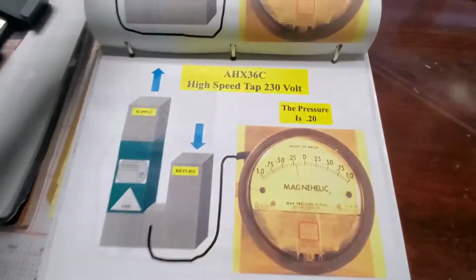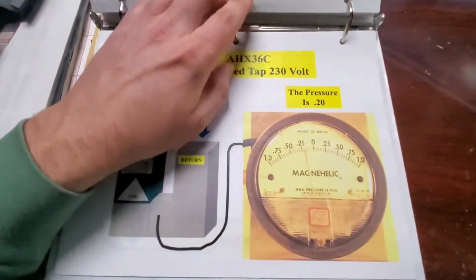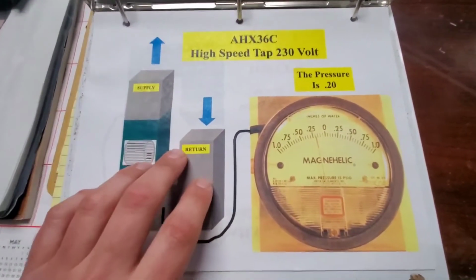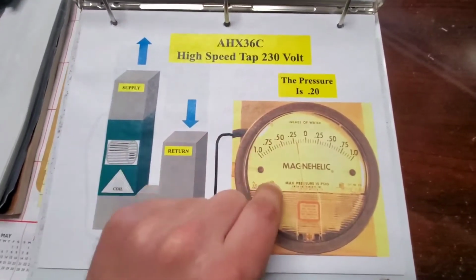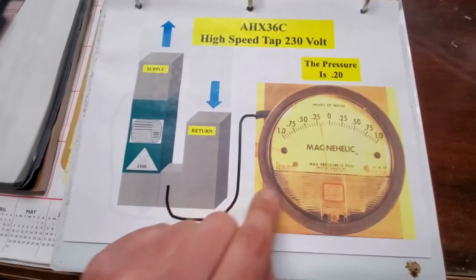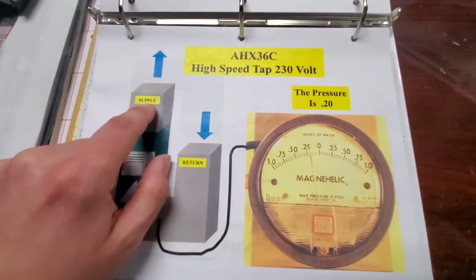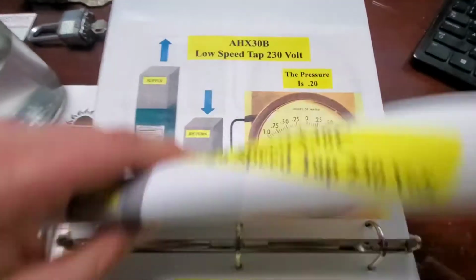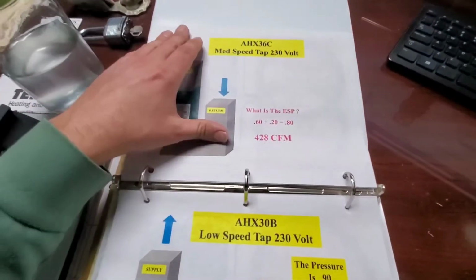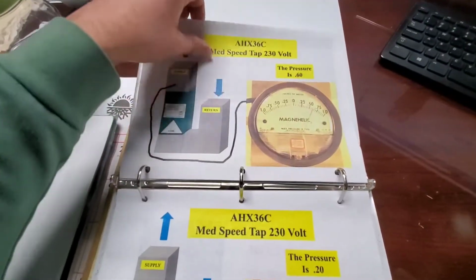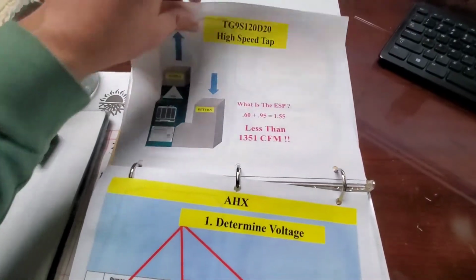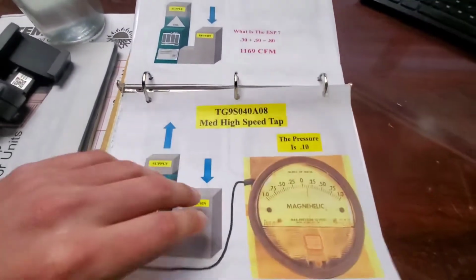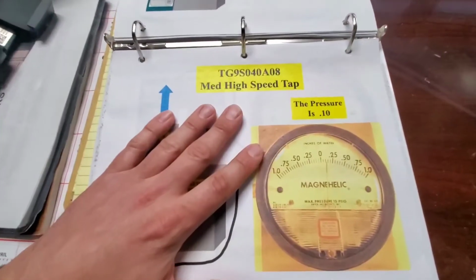Now there's one more thing I want to show you, and that is if you want to measure static pressure and you have a real technician that is working on your equipment, he's going to have a magnehelic. That magnehelic, he's going to be able to measure the return and the supply to get the total external static pressure, okay? And what you want to do is measure the static pressure and determine the airflow that you need, okay? So really good information, and I hope you guys enjoyed the video.